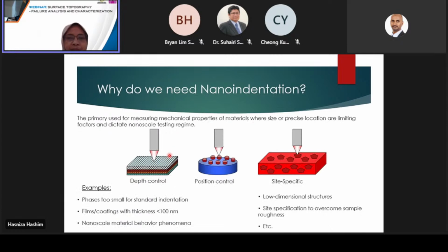So why do we need nano indentation? The primary objective of using nano indentation is to measure the mechanical properties of material where the size or precise location are limiting factors. As an example, if you have a very thin layer and you want to know the hardness and modulus of the top layer, we need an instrument that can control the depth of penetration in a thin film. We must take care when indenting a thin film to avoid also testing the properties of the underlying layers. Another reason for nanomechanical testing is to test at very specific sites with very fine precision and control. So it can only be done if you do the testing using nano indentation techniques.